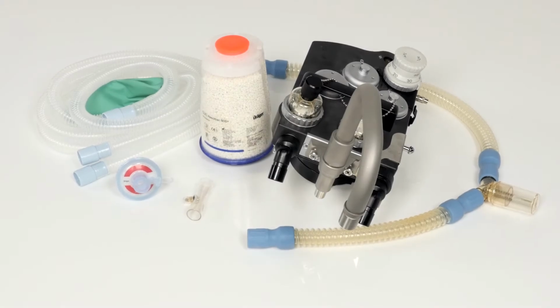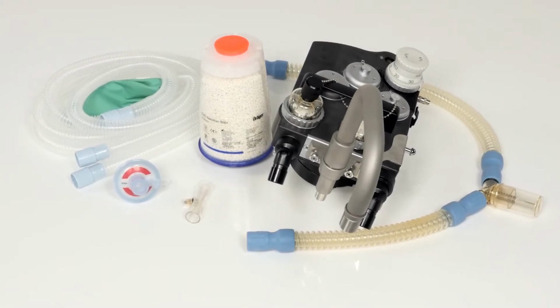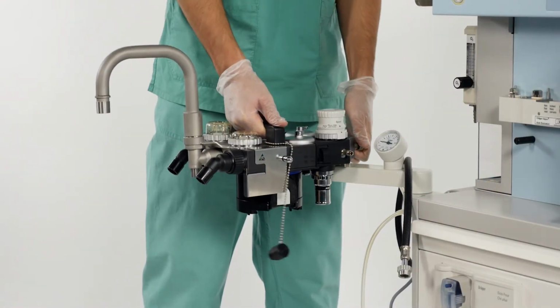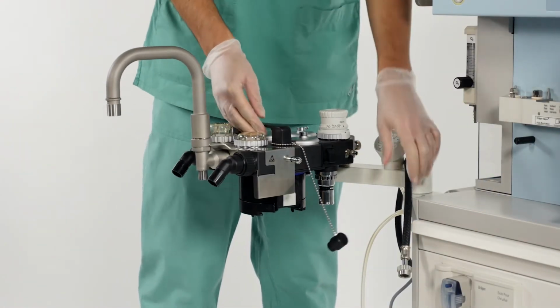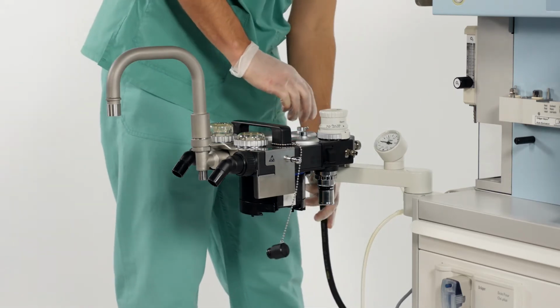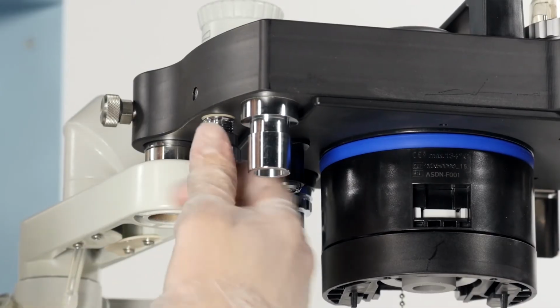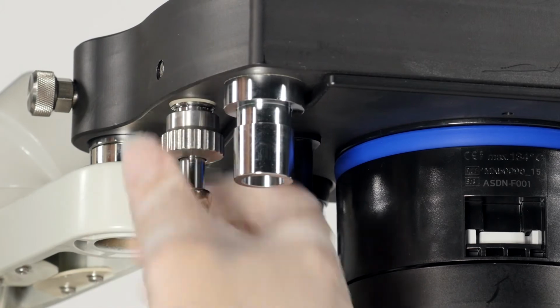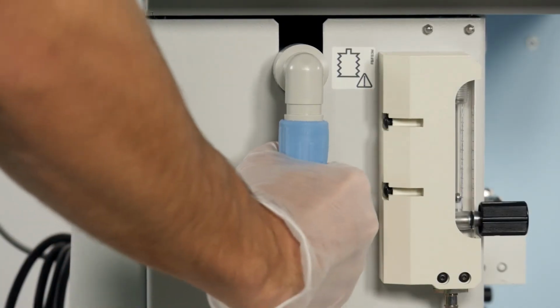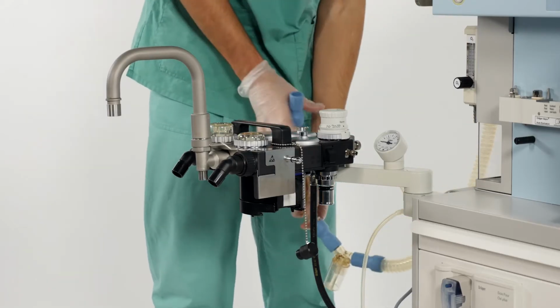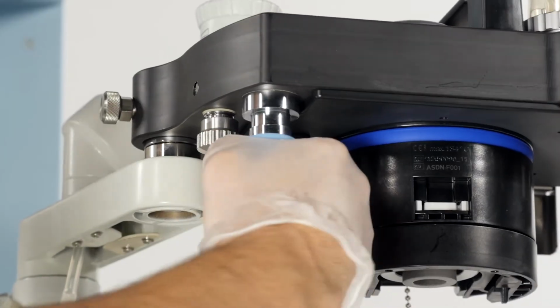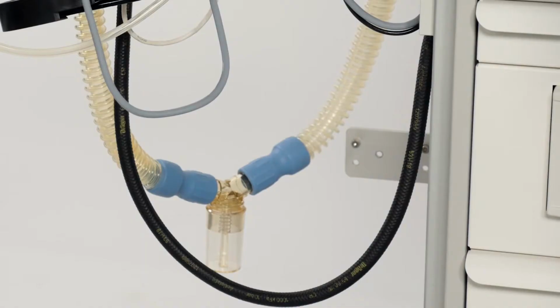For preparation of the breathing system, make sure that all parts are present. Fit the compact breathing system onto the mount, located on the mounting arm. Connect the fresh gas hose from the Fabius to the compact breathing system. Attach the ventilator hose to the ventilator and to the conical connector port on the underside of the COSY. Make sure that the water trap is at the lowest point of the connection.